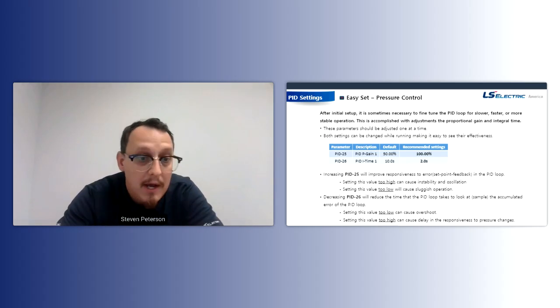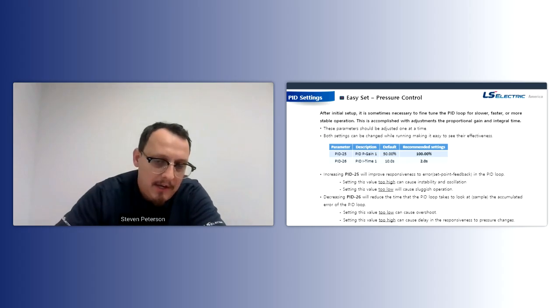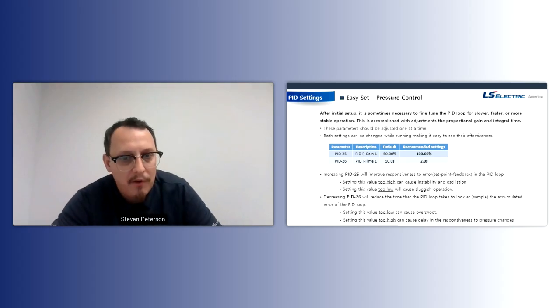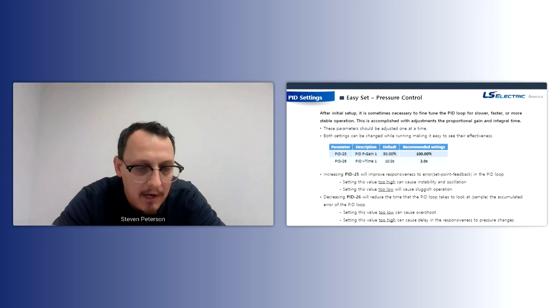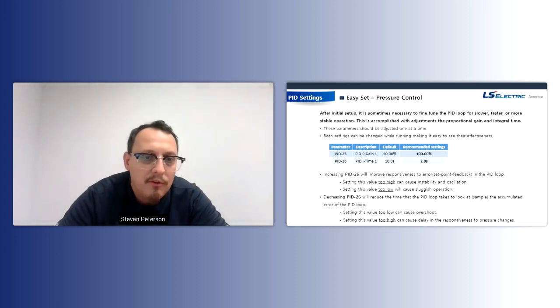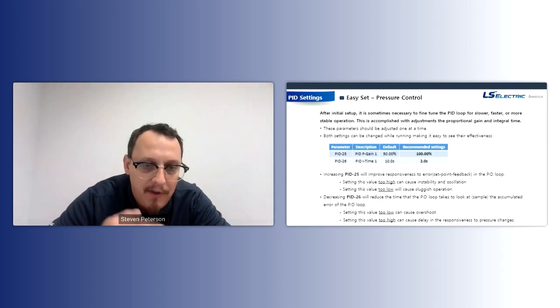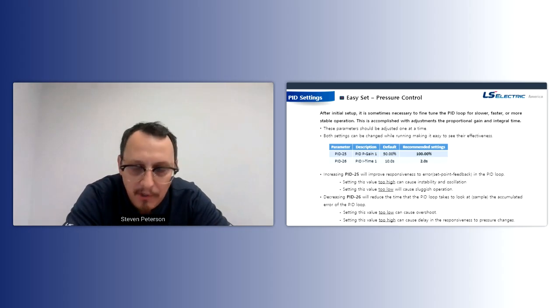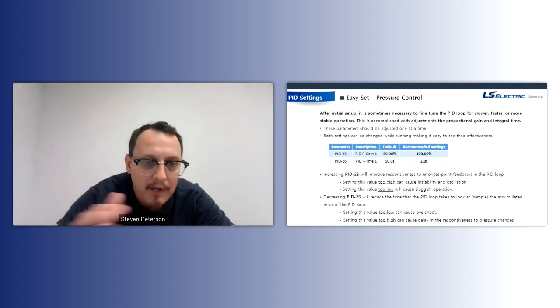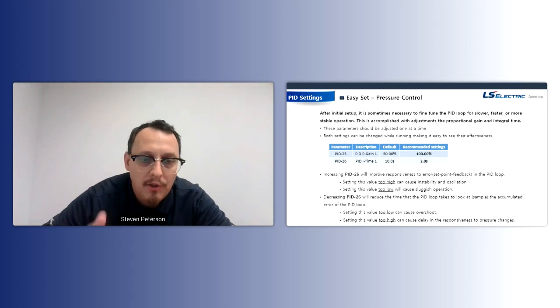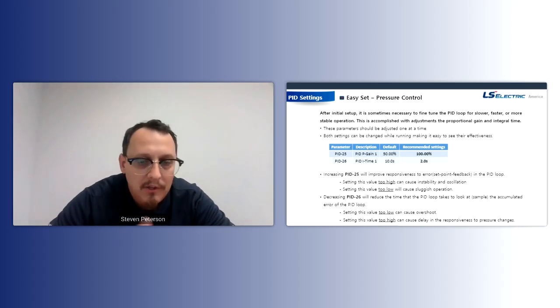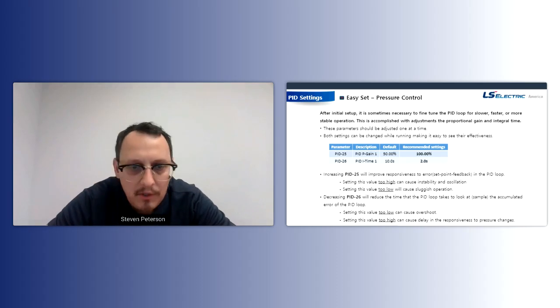Next thing I would do is the I time. You can think of the I time as like a sampling rate. It's like how often are we checking the accumulated error between that set point and that feedback. So the shorter the I time, the faster it's going to respond because that sampling rate is shortened. It's happening quicker. So if you left this at like 10 seconds, that's kind of like a long delay. We're checking the error amount every 10 seconds. So you could set this at typically 1 or 2 seconds and it'll respond pretty well. Okay.